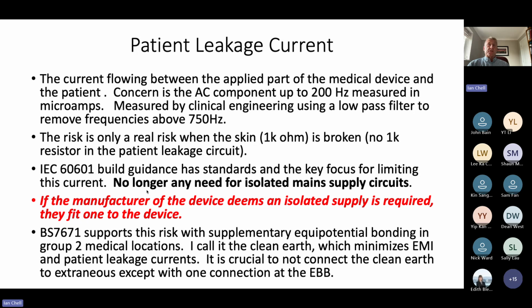And when clinical engineering are measuring this, they use a low pass filter to remove the frequencies above 750, so there's no RF. And the reason they do this is because the heart is susceptible to AC currents around the 50 hertz mark or about that. Okay, so that's the risk. If we had DC mains, we wouldn't have such a problem.